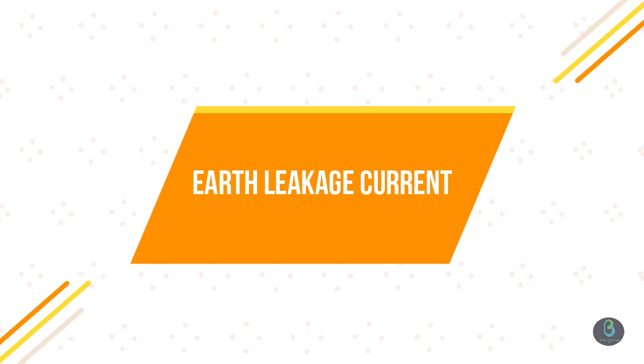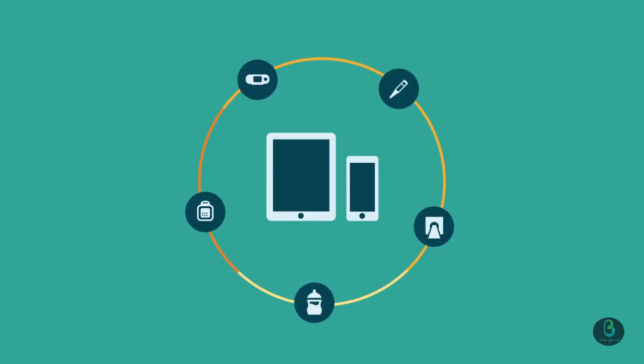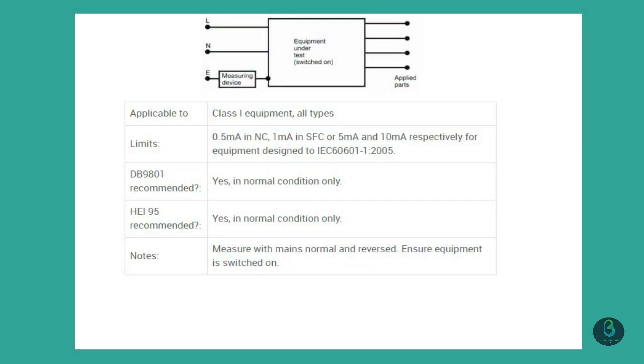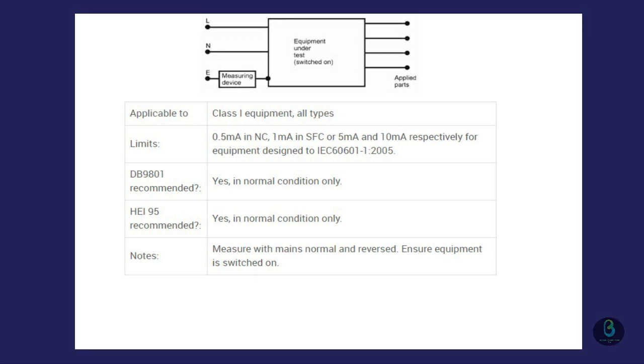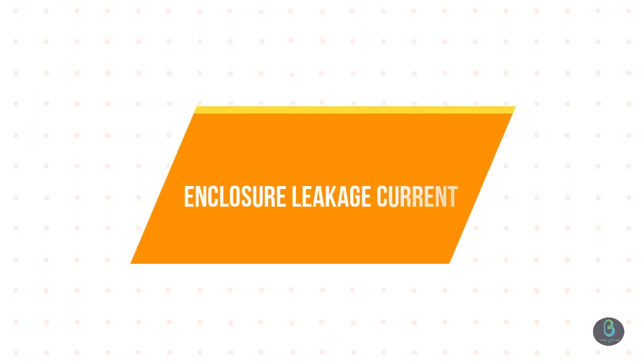Earth Leakage Current. For Class 1 equipment, earth leakage current is measured as shown in Figure 12. The current should be measured with the mains polarity normal and it is recommended that the earth leakage current be measured in normal condition only. Many safety testers offer the opportunity to perform the test under single fault condition, Neutral Conductor Open Circuit. This arrangement normally gives a higher leakage current reading.